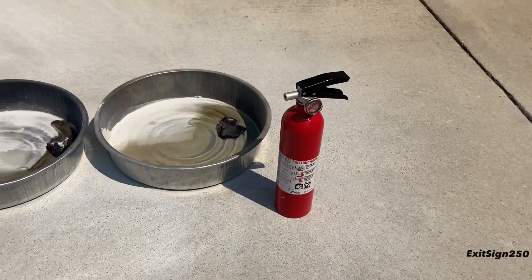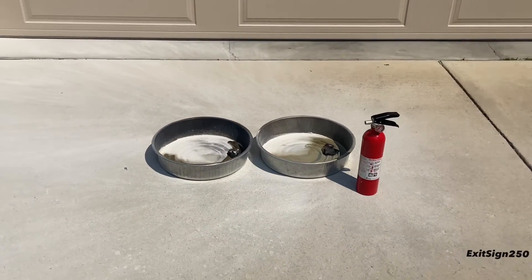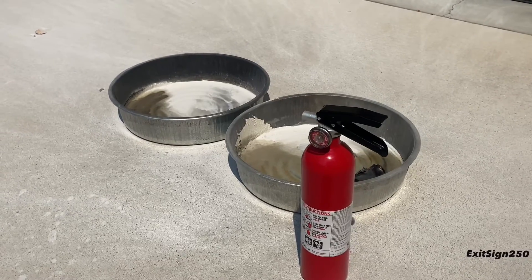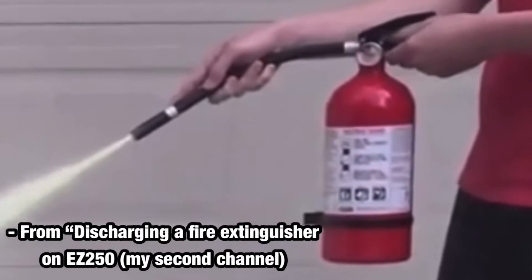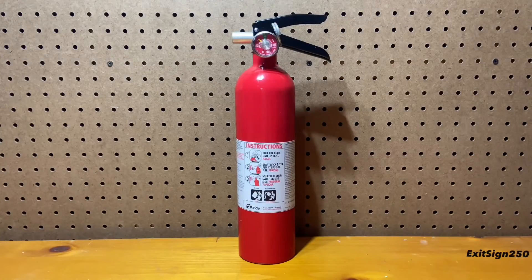As you saw, the Kidde Pro was able to control and extinguish the fire. The extinguisher operation was good. The lever was easily squeezed and the extinguisher was able to stop discharging when released. The reason I mention that is I've had problems with previous Kidde models with this same valve not being able to stop discharging when it was released — not really ideal when you need the extinguisher to stop spraying.